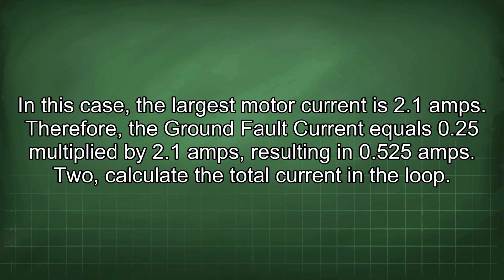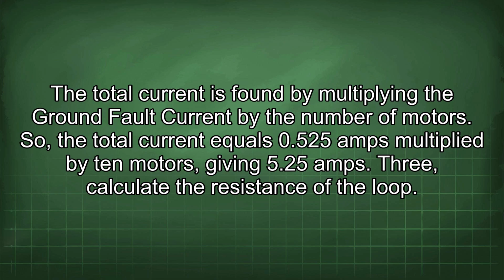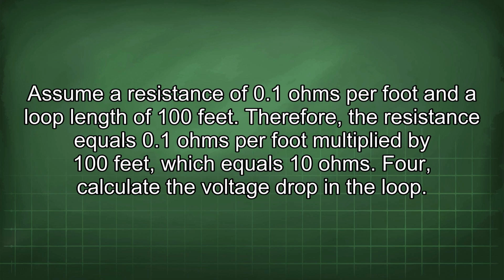0.525 amps. 2. Calculate the total current in the loop. The total current is found by multiplying the ground fault current by the number of motors. So, the total current equals 0.525 amps multiplied by 10 motors, giving 5.25 amps. 3. Calculate the resistance of the loop. Assume a resistance of 0.1 ohms per foot and a loop length of 100 feet. Therefore, the resistance equals 0.1 ohms per foot multiplied by 100 feet, which equals 10 ohms.